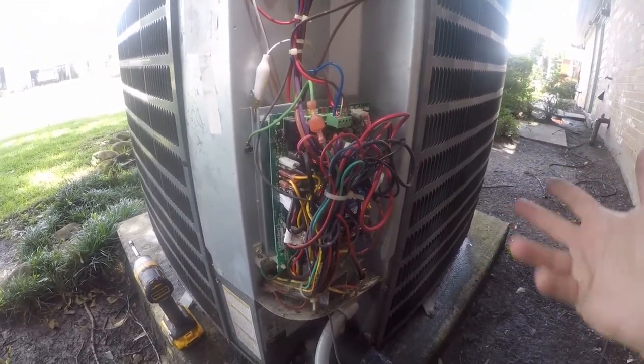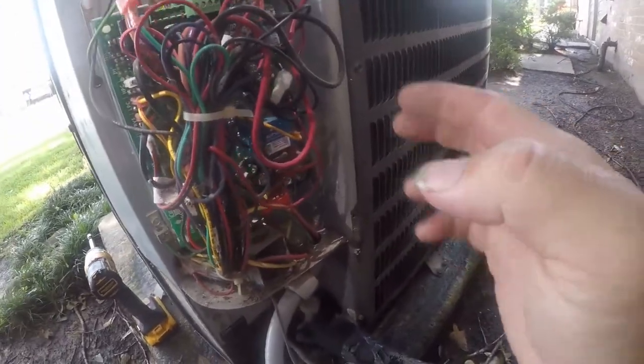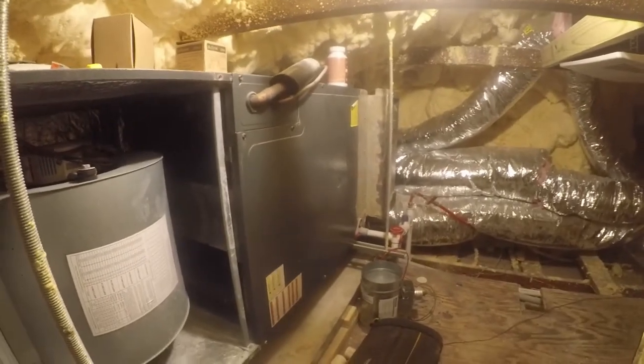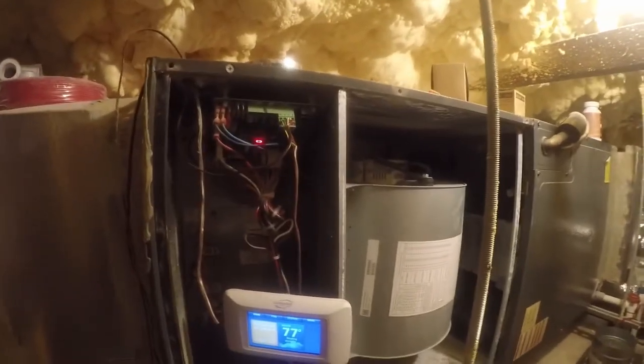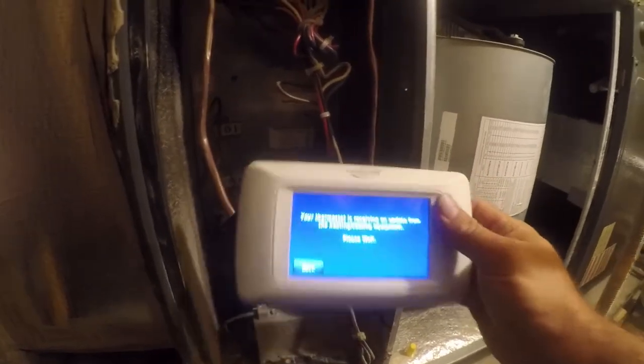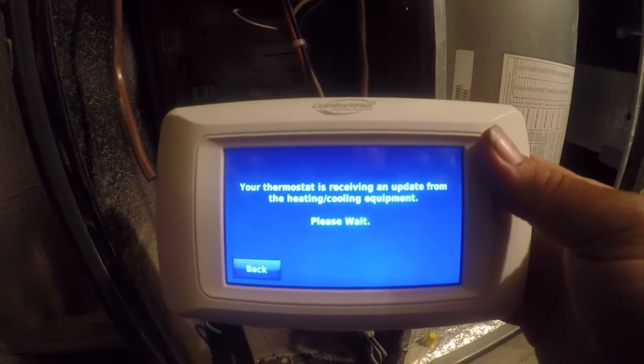Here's the exterior unit. One of the things I did is disconnect the thermostat and hook it up to these four terminals here — it can see the condenser but it can't see the blower. I had these wires disconnected at that time, and if I hit the test button this will come on. So I've got the thermostat hooked up directly here and just reconnected the communication wire out to the condenser. I'm set up more like a commercial unit because I just didn't have room for an air return the way I wanted, so I'm using the attic as an air return — which is fine because this is a spray foam insulated house and it needs to be conditioned. It says a blower was not detected. I'm going through a reset, and it's been displaying this error, which is basically the death of the communications network as far as I can tell based on other people's experiences.